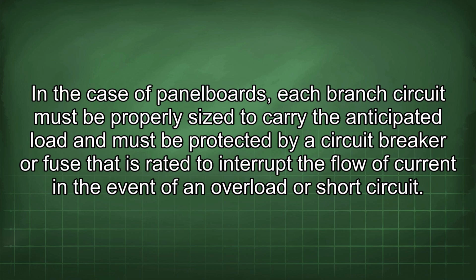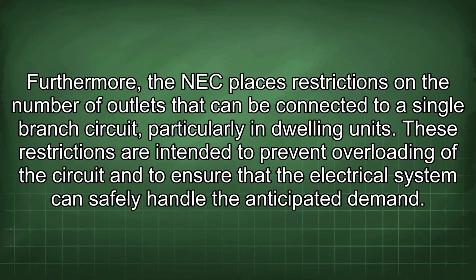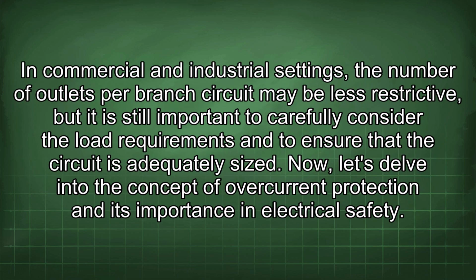In the case of panel boards, each branch circuit must be properly sized to carry the anticipated load and must be protected by a circuit breaker or fuse that is rated to interrupt the flow of current in the event of an overload or short circuit. Furthermore, the NEC places restrictions on the number of outlets that can be connected to a single branch circuit, particularly in dwelling units. These restrictions are intended to prevent overloading of the circuit and to ensure that the electrical system can safely handle the anticipated demand. In commercial and industrial settings, the number of outlets per branch circuit may be less restrictive, but it is still important to carefully consider the load requirements and to ensure that the circuit is adequately sized.